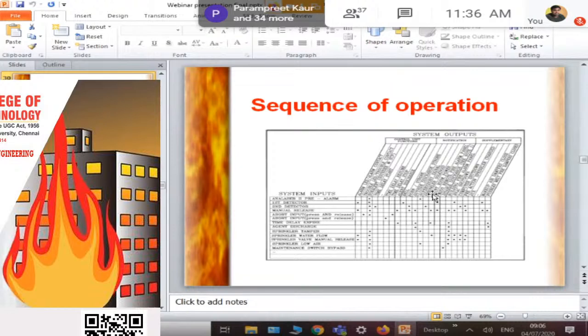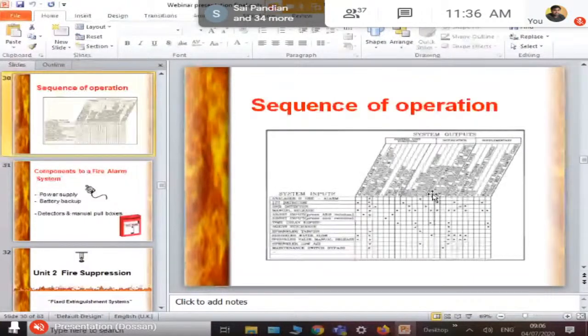Again, this is purely based on rating. Say you have a 15 floor building, and you cannot have all the floors evacuated all of a sudden because there is a fire on the 10th floor. So obviously you have to do it zone wise, because your occupancy, say the 15th floor, is having 1500 people or a couple of elevators. You cannot escape. You will have to separate it zone wise.